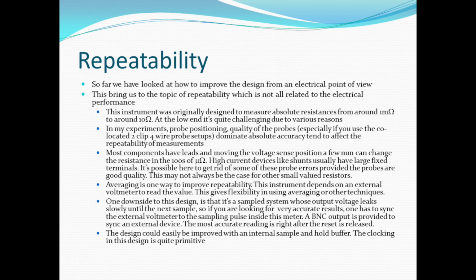So this brings us to the topic of repeatability. We have looked at how to improve the design from an electrical point of view, but repeatability for these types of low value resistances is probably more important when you get into the sub-milliohm realm of absolute measurements. Originally this was designed to measure absolute resistances from around a few milliohms to 10 ohms. At the low end is where I have most of the problems in meeting the accuracy because of the residual offset and any gain errors that are left over.